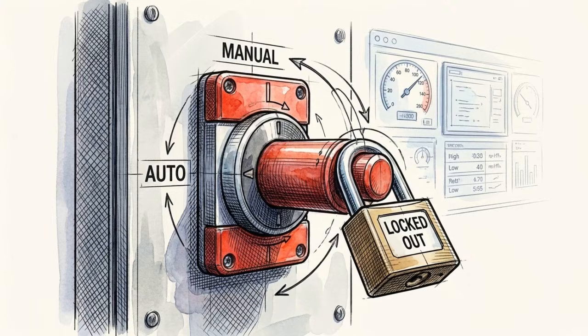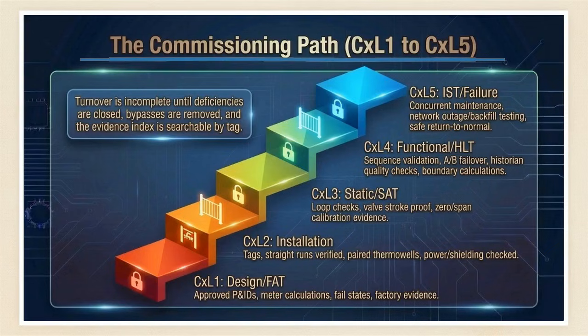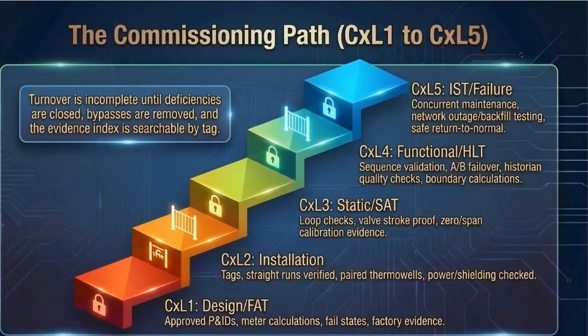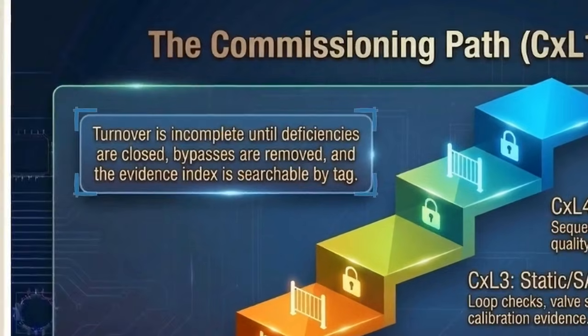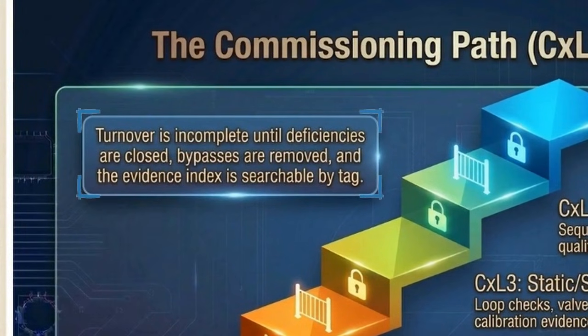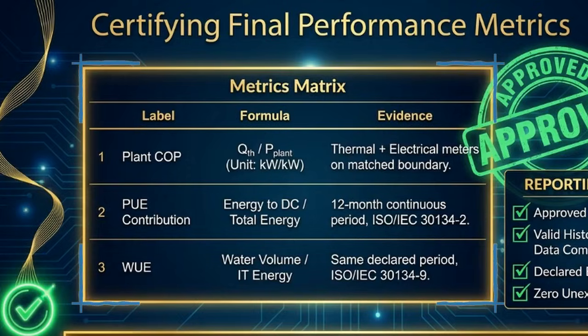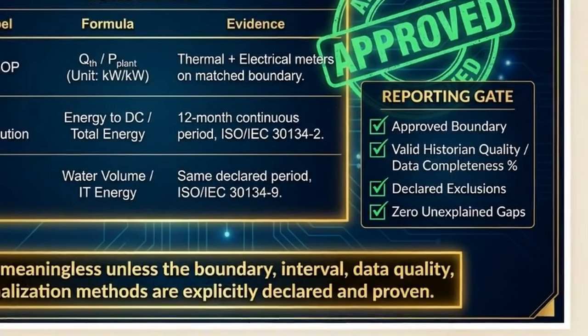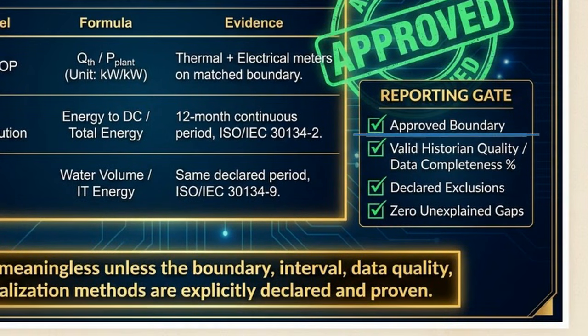This staircase outlines the commissioning path to bring the measurement architecture online, moving from initial design up through failure testing at level 5. Project turnover remains incomplete until all physical deficiencies are closed, temporary bypasses removed, and the evidence index is searchable. This matrix displays the final reporting gate for efficiency metrics like plant COP, PUE, and WUE. It verifies no metric is certified unless its physical boundary, continuous 12-month interval, data completeness, and normalization methods are explicitly proven, with 0 unexplained gaps.